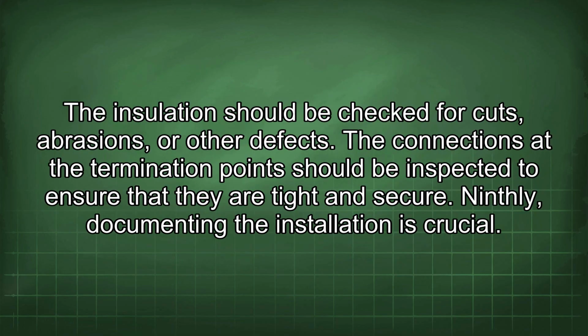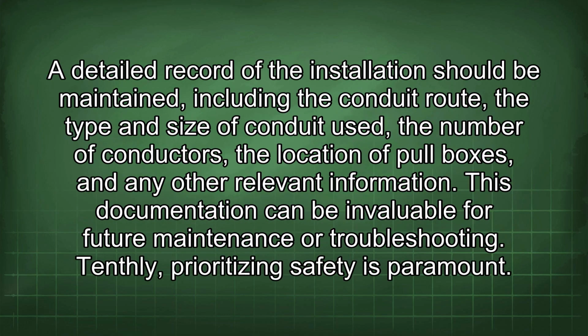The insulation should be checked for cuts, abrasions, or other defects. The connections at the termination point should be inspected to ensure that they are tight and secure. Ninthly, documenting the installation is crucial. A detailed record of the installation should be maintained, including the conduit route, the type and size of conduit used, the number of conductors, the location of pull boxes, and any other relevant information. This documentation can be invaluable for future maintenance or troubleshooting.